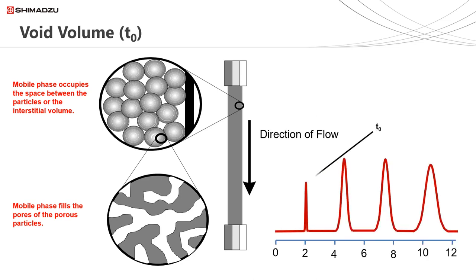Looking at the chromatogram on the screen as an example, the peak at two minutes is marking our void volume. The time this peak takes to elute is known as T0. In reverse phase HPLC, we often use uracil as an unretained analyte to calculate the void volume at T0. At a flow rate of one millilitre per minute, a two millilitre void volume would give a T0 of two minutes. Increasing the flow rate would decrease the value of T0, and decreasing the flow rate would increase the value of T0, but the actual void volume remains constant.